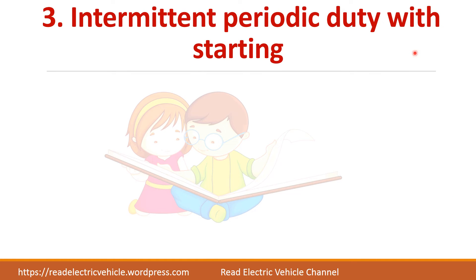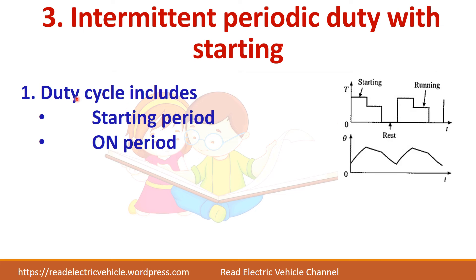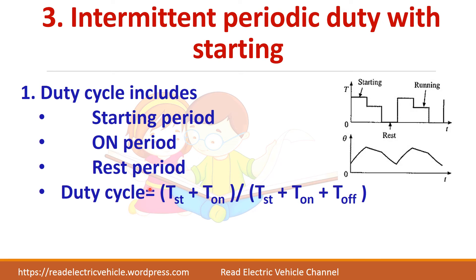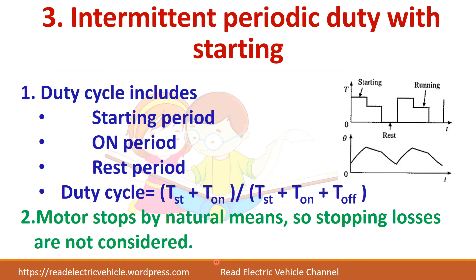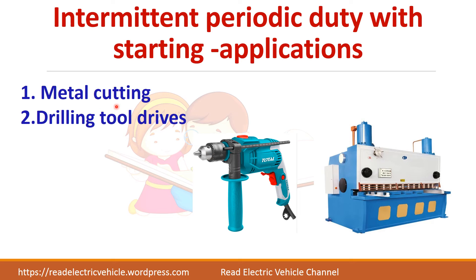Next is intermittent periodic duty with starting losses taken into consideration. Here, the load has a starting period, then a running period, and a rest period. The duty cycle is given by the starting period plus on period divided by the total time period — that is, starting plus on period, divided by starting plus on period plus rest period. We consider only the starting period because stopping of the motor is very fast or occurs by natural means. In case the braking period is also large, we have to consider those losses as well. Applications include metal cutting, drilling, and machine tools.